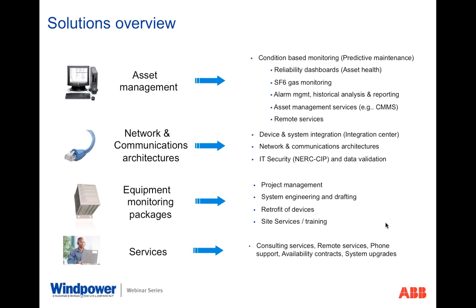Due to the old technology of equipment in the substations, communication has now become a greater issue. How can we get the asset information to a centralized asset management system due to the lack of communications at the substation level? There are potential concerns with the bandwidth and even the challenges surrounding NERC CIP compliance. Typical breaker monitoring packages are non-operational data that can be separated from traditional SCADA equipment to eliminate any compliance issues with NERC CIP. But this does not eliminate all the challenges of the lack of infrastructure. Options such as wireless communications become more apparent in the efforts to design the proper architecture.